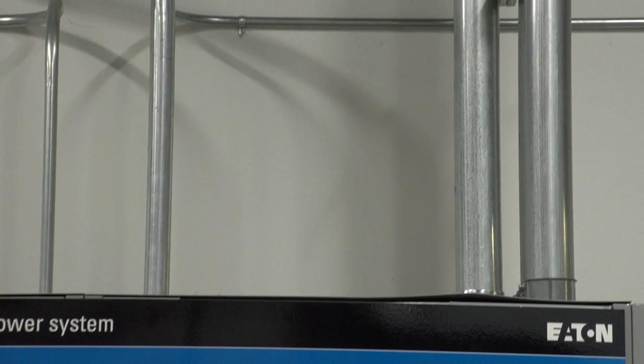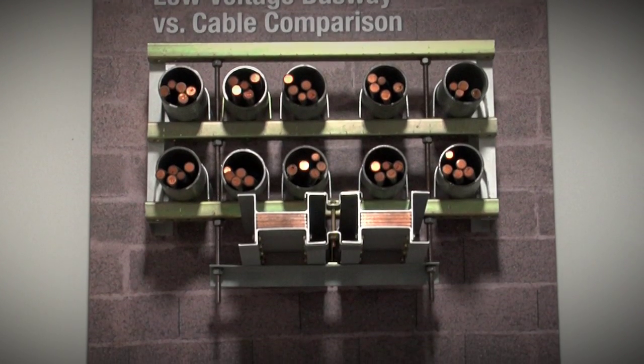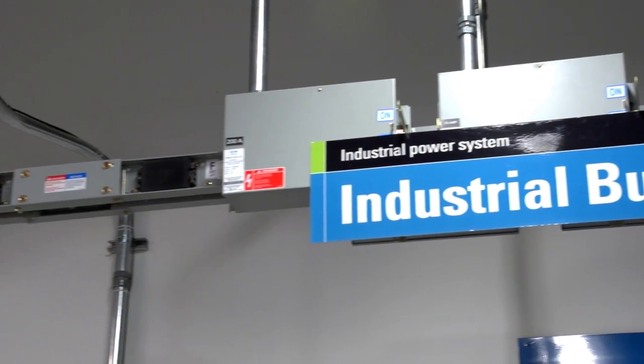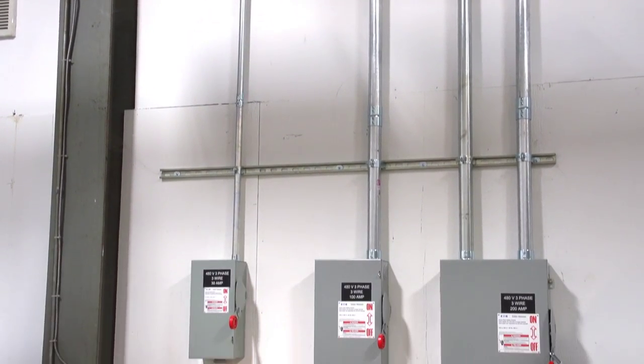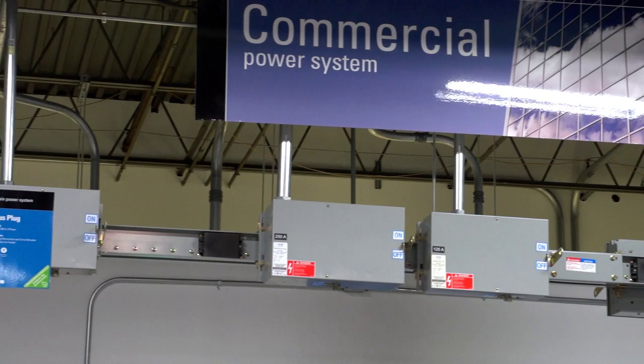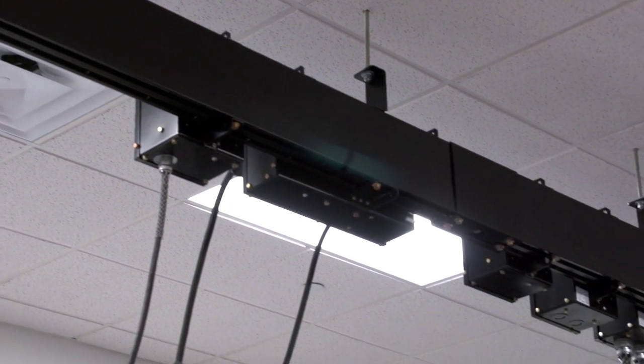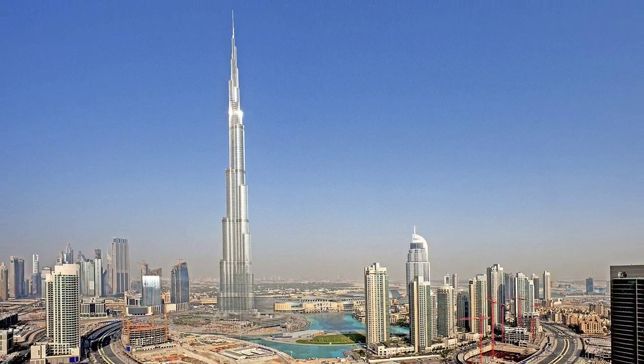From the main IFS, power is distributed via conductors in conduit to sections of busway. This 400-amp busway is connected to the rest of the system via the termination section at this end. The rest of the busway is mostly made up of special copper bus bars called sandwich bus, because they're dipped in epoxy insulation and sandwiched directly together to form a three-phase power distribution channel. Busway is very popular as a flexible option for industrial plants where equipment is frequently relocated. At two-foot increments, bus plugs are used to connect local loads like these three safety switches. The bus plugs provide a breaker for protection and allow easy reconfiguration if a piece of equipment is moved to another part of the facility. Busway is also an efficient way to distribute power in large commercial buildings — for example, the Burj Khalifa literally has miles of Eaton busway running through the building.